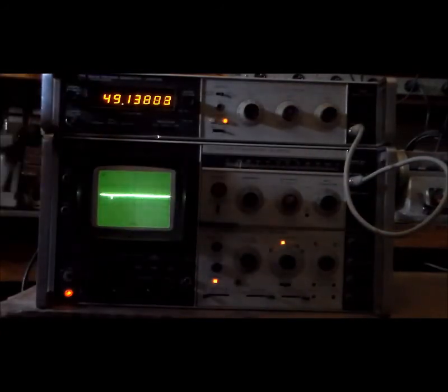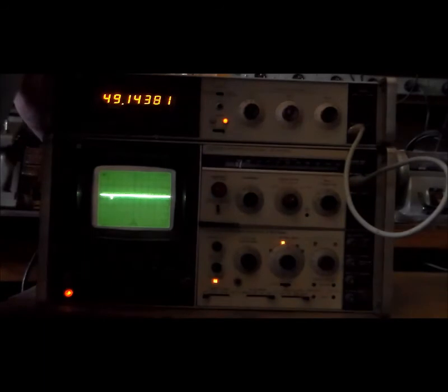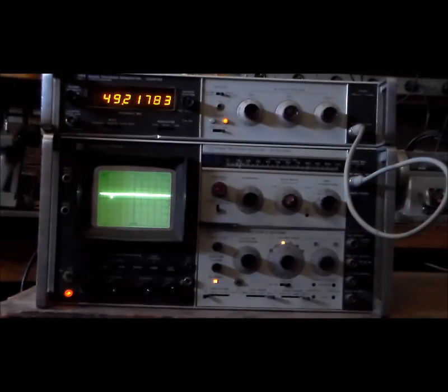Now, trouble. The trouble comes from intermittent connections in these cables. There's only one, but if I wiggle this, you can see that anomalies can develop. Okay, so I think it is just dirty contacts in both the analyzer and the end of the cable. And there is no restraint on that connector. So that is the number one cause of problems, aside from operator error.